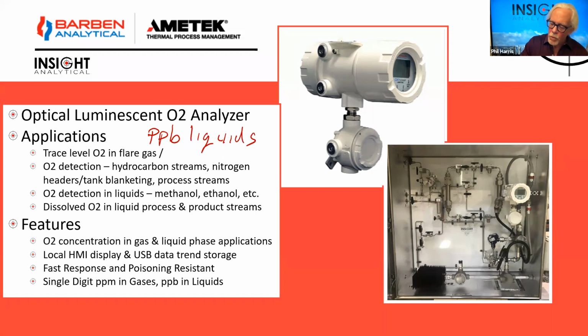So we can do oxygen in boiler feed waters, for example, and down to single digit parts per million levels in gases. So common applications we'll see for these are oxygen levels in flare gas or in vapor recovery units. We've done oxygen measurements in actual hydrocarbon streams, like in propane, in crude oil. We've also used this as an oxygen measurement for leakage into tank blanketing applications. It's got almost no interferences and is extremely resistant to most chemicals. There's a couple of things it doesn't like, which are aromatic hydrocarbons, but we've even done applications measuring oxygen in 55% H2S streams.